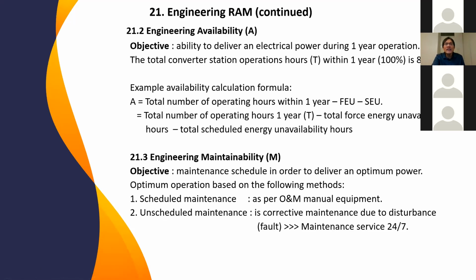Availability to deliver, the objective is the ability to deliver electrical power during 1 year of operation. 1 year of operation is equivalent to 8,760 hours. Example availability calculation: we calculate the number of operating hours theoretically as 8,760 minus forced energy unavailability minus scheduled energy unavailability.